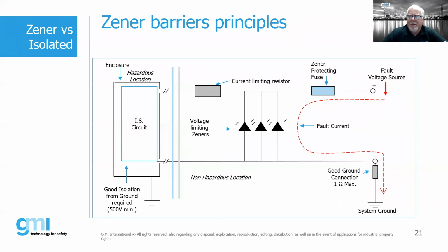So some people will ask the question, well, what's the difference between a barrier that's suitable for IA and a barrier that's suitable for IB? Well, it's basically the redundancy. That's what it is. There is also another big difference, Bob, that sometimes this resistor, the current limiting resistor, is the only accepted method of protection for IA. You can only use a resistor to limit current, whereas in IB, you can do other active types of limitation, which allow you to have more power into IB.